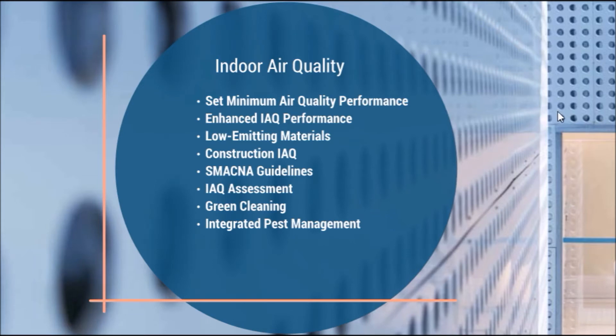Enhanced IAQ performance involves setting a permanent entryway system 10 feet into or out of a building to collect dirt and debris — basically a permanent floor mat. For exhaust, we want to minimize exposure from garages, laundry rooms, and copy rooms. For filtration, vents that supply outdoor air must have particle filters meeting a MERV standard of 13 or higher. For ventilation, we want to increase it 30% above the minimum, monitor CO2, and have naturally ventilated spaces under CIBSE AM10 guidelines.